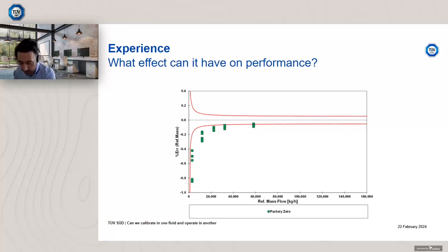Well, we complete a lot of R&D here at NAL, and one such program of work we looked at was a Coriolis meter with differing zero values. So Coriolis meter manufacturers often have a water calibration facility that's fully traceable. They all have a water calibration facility, and whether that's fully traceable or not. When the device is manufactured, they will calibrate it in their water facility and get their flow calibration factor. And when they do that, they'll also zero the device.